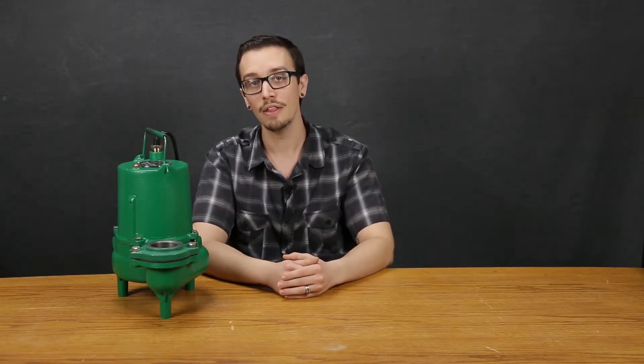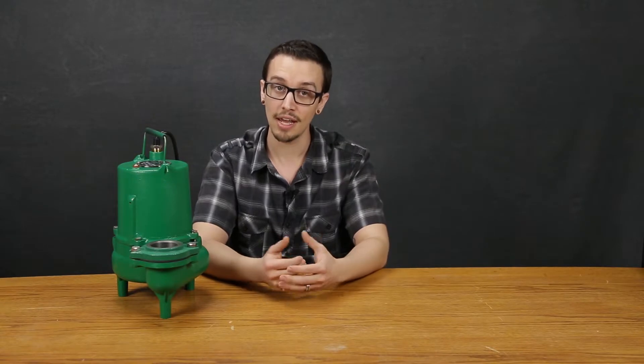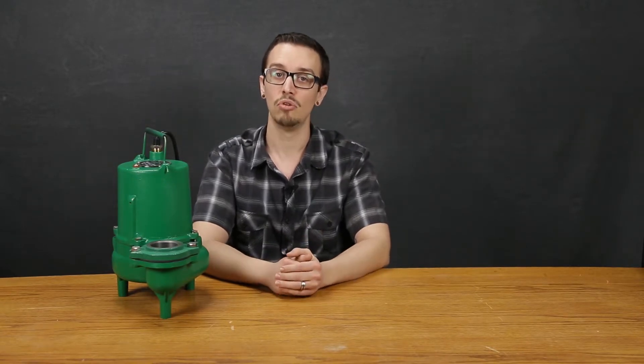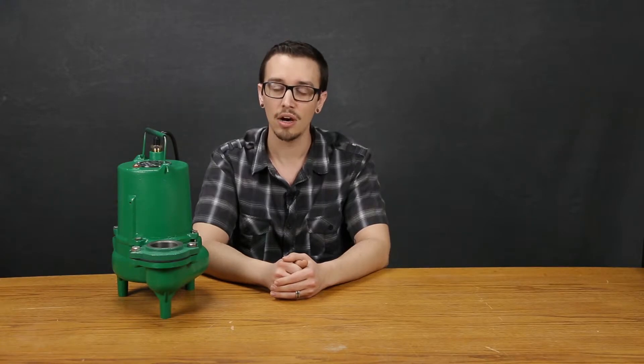The Myers MSK50 boasts a half horsepower motor that comes in 115 or 230 volts and is rated at 12 or 6 full load amps respectively. At the standard 1750 RPM, the pump can produce 24 feet of head and a maximum flow rate of 115 gallons per minute.